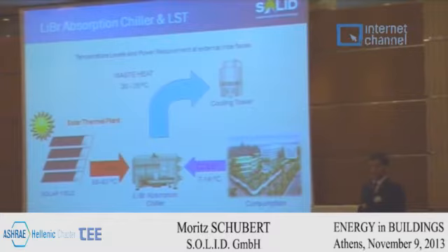And also it is very good if the distribution system in the building can reach a rather high delta T, up to, let's say, 14 degrees centigrade. In Singapore, the one we installed, we can even deliver cold at 16 degrees. So, you can see from these figures, a building like that needs to be quite well designed, but that's what we recommend anyway: when you go for a solar cooling system, you always also have to look at the distribution system, benefit from passive measures on the cooling load, optimize the cold generation system, and then, when you've done this, you also integrate a solar cooling system.